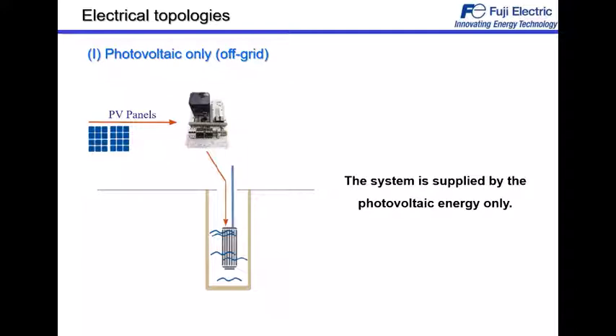The first one is off-grid. As the name says, we have a solar system feeding the drive, and this drive is feeding the pump. Since the only energy coming to the drive is through the PV panels, the PV system, we can pump only when there is energy, only when there is enough sun, enough radiation.